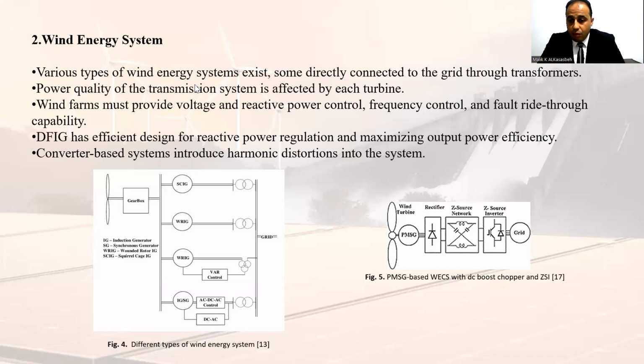The first type has a squirrel cage induction generator connected to the grid, and the second one is a wound rotor induction generator. The third type is a wound rotor induction generator with controller. The fourth one is an induction generator or synchronous generator with control and with a converter connected to the system. There is another type, the full converter system, which is a permanent magnet synchronous generator based wind energy conversion system with a DC boost and ZSI. We can also see a turbine connected to the permanent magnet synchronous generator and to the converter, and after that connected to the grid.